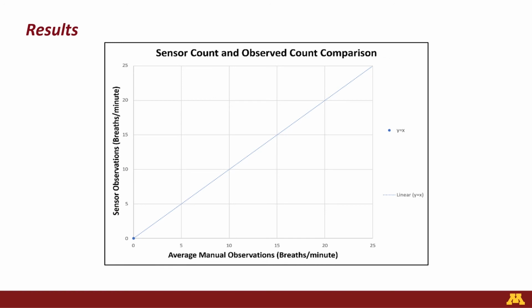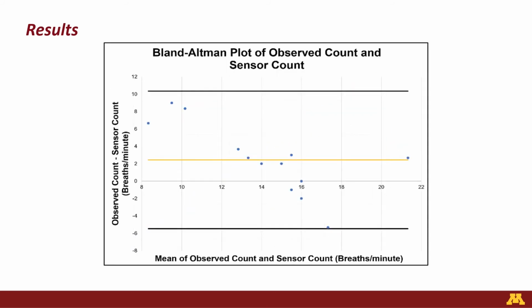Sensor count and observed count comparison was conducted with a y equals x line. Average manual observations are seen on the x-axis and sensor observations on the y. The closer the values are to the x equals y line indicates more agreement between the 2 methods of counting breaths. Below the line, the sensor was undercounting. Above the line, the sensor was overcounting. Observers on average counted 2.44 more counts than the digital zero crossing sensor.